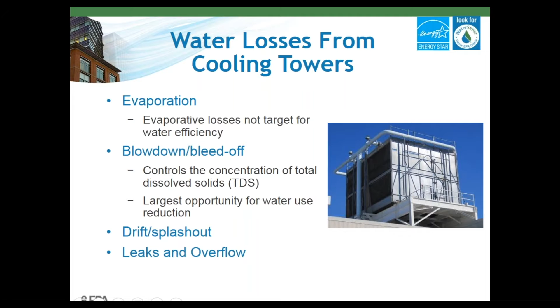So to maximize the water efficiency of your cooling tower, you really want to pay careful attention to the quantity of makeup water and blowdown water being used. Especially if you can equip it with meters. If you don't have meters, consider installing them. You don't know what you don't measure. So sub-metering, as Tara was talking about earlier, is really important for making sure that you actually know and can benchmark and improve your benchmarks on your system.